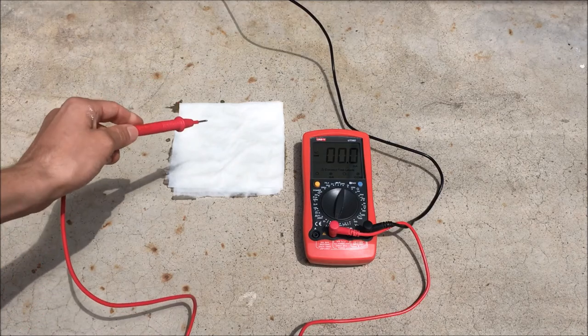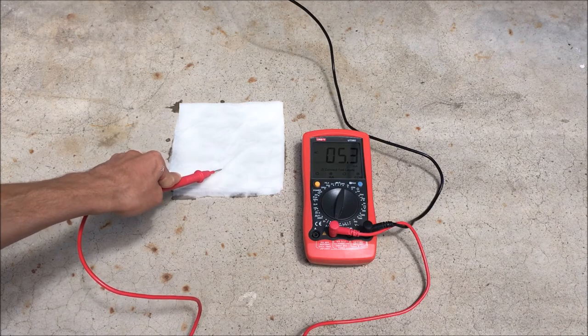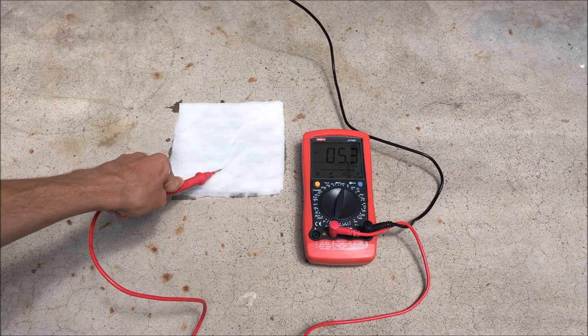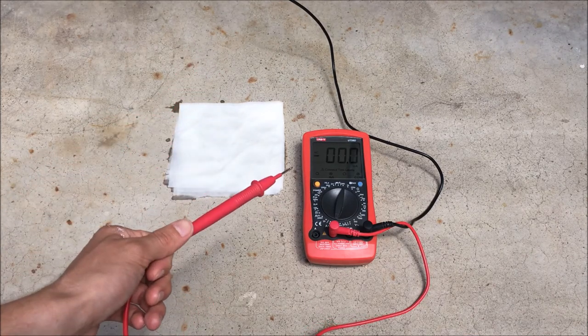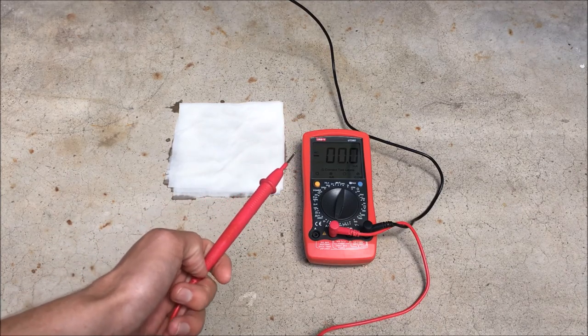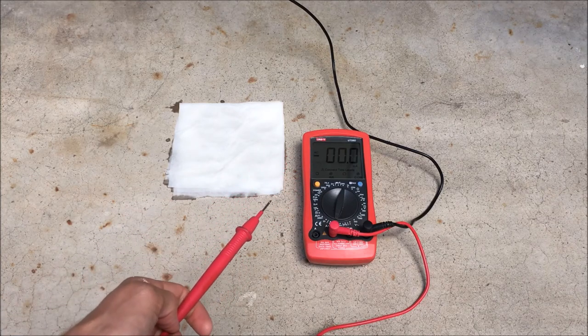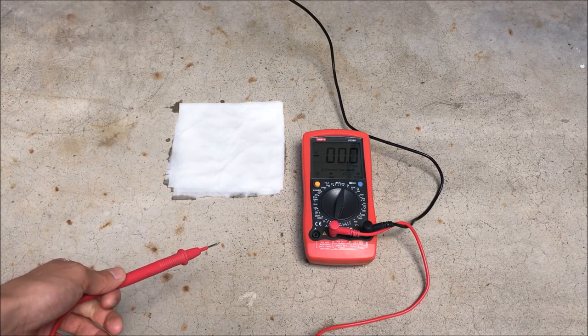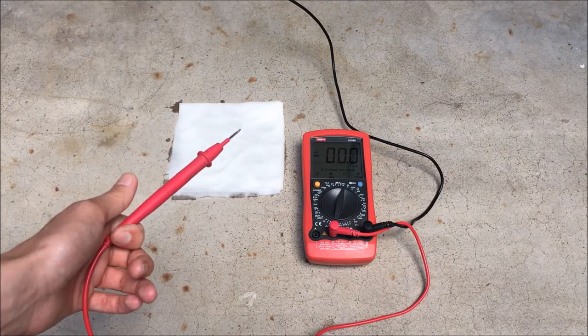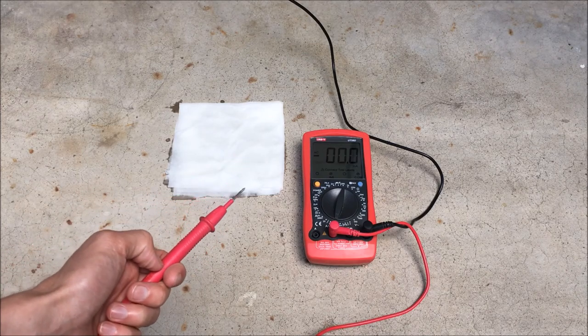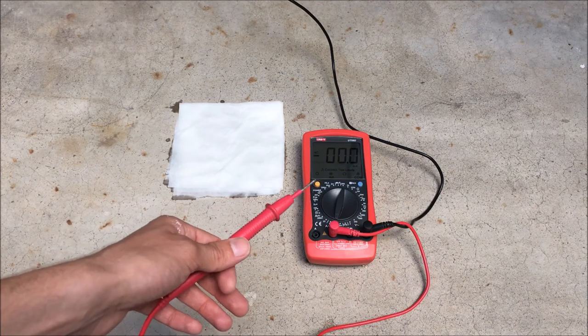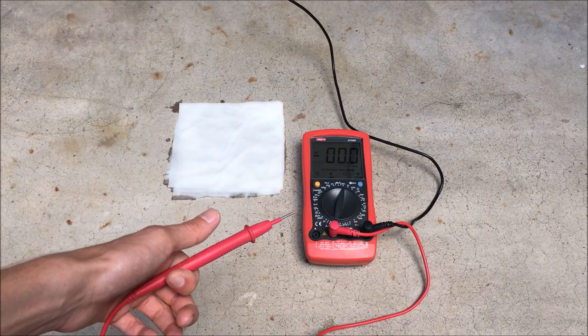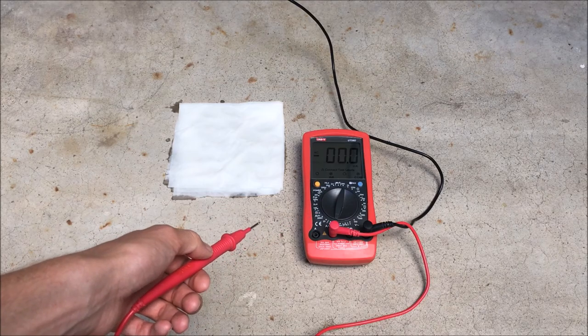If I connect this to the paper towel you can see that up to 5.3 milliamps of current flows. Now that's a considerable amount. Not quite enough to be hazardous but it certainly would give you a nasty shock if you touched it. This is an important thing to notice that if you have a puddle of water on concrete and you're standing in it you have a relatively low impedance path to ground. So keep that in mind when you're thinking about what electrical shock hazards are present in your work area and whether you need to take greater precautions such as avoiding contact with the circuit altogether or wearing insulating clothing or boots.